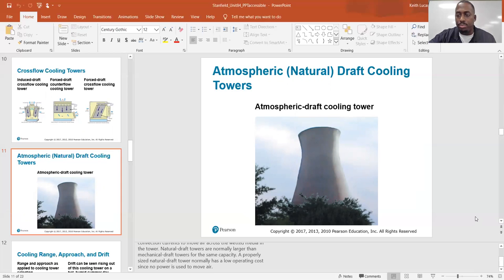The tower fan is wired to allow cycling by a tower thermostat to maintain the proper condenser water supply temperature. So here we have our cooling tower with a fan and pump — this is the starter for the cooling tower fan and pump, which is first in the lineup. That gets going and makes sure we have water flow to our condenser. Then next in line is our compressor starter. Once that starts up, the system is on and running — pumping refrigerant and actually cooling. But we do not want this compressor on if there's nothing cooling this condenser, because again your head pressure will shoot through the roof.